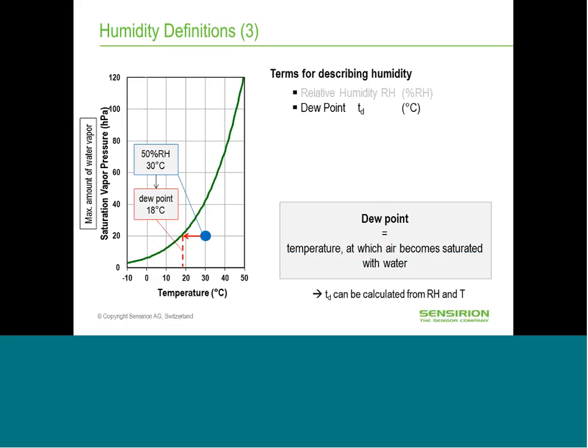Another very often used term for describing humidity is the dew point. It's TD, and it's actually a temperature, so it's given in degrees centigrade, but it is a measure for the humidity. And the dew point is actually the temperature at which air becomes saturated with water. So if you have a room, for example, again, we take this blue dot, 50%, we have learned on the slide before, at 30 degrees, the dew point indicates to which temperature we have to cool down this air, these conditions, until we reach saturation.